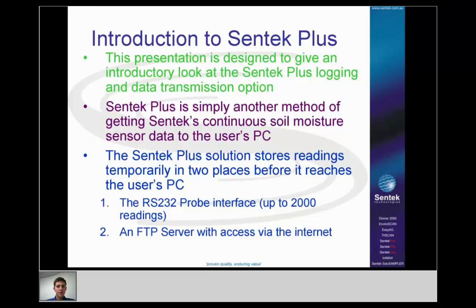The Sentek Plus solution stores readings temporarily in two places before it reaches the user's PC. The first is the RS-232 probe interface, where it can store up to 2,000 readings — one per sample, regardless of how many sensors are on the probe. Those readings stay there until a successful upload is done to the FTP server, which is the second place data is stored. When that upload is successful, the readings are deleted from the probe interface.